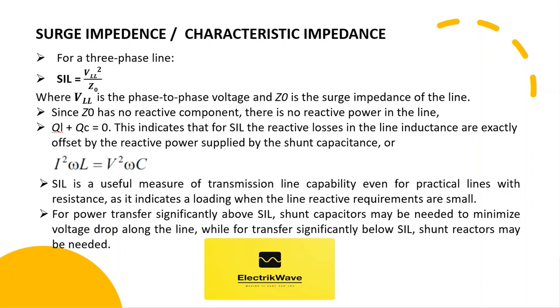This indicates that, for SIL, the reactive losses in the line inductance are exactly offset by the reactive power supplied by the shunt capacitance, or I²ωL equals V²ωC. SIL is a useful measure of transmission line capability, even for practical lines with resistance, as it indicates a loading when the line reactive requirements are small.